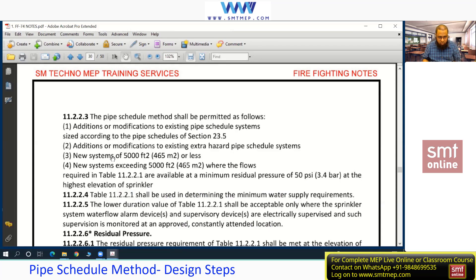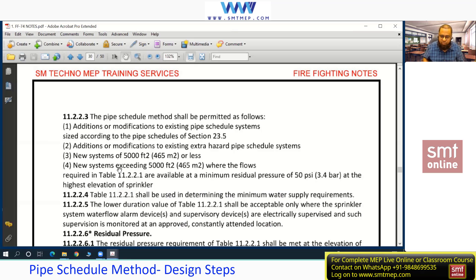One more point: for extra hazard, the pipe schedule method is generally not applicable for new projects. However, if it is an addition or modification to an existing extra hazard system, we can use this pipe schedule method for that existing project or modification.